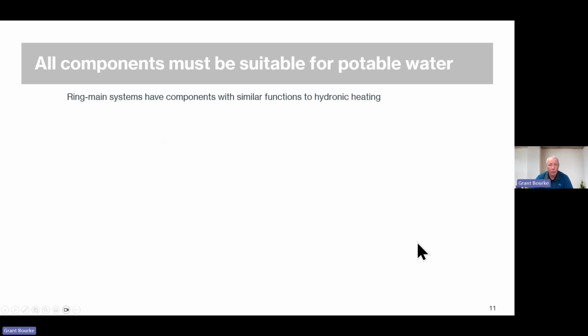So when we're into ring mains, we're into some components that have got a lot of similarity with hydronic heating. And the hydronic heating components aren't certified for potable water. Often suppliers have similar looking components for hydronic heating and for potable water that aren't certified for both applications. And the hydronic heating ones are normally cheaper. They're not lead-free brass and so on.